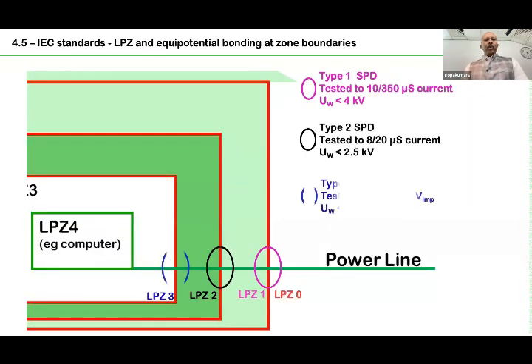So what do we do? At the main distribution board, technically, if you read the standard, it says between zone 0 and zone 1. Very simple. At the main distribution board, you have to put an SPD. And that particular SPD is called a type 1 SPD. See here, type 1 SPD. From the color you can identify it.